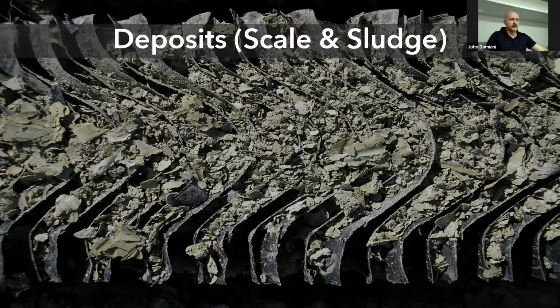Basically, a deposit is just a general term for anything that is depositing onto a surface, usually a higher skin temperature surface, so like where the heat transfer occurs, for example. So these are deposits that we don't want on the system, because a deposit is an insulating barrier to heat transfer. So if we're trying to transfer heat from a cooling system, we're trying to reject heat into the atmosphere inside the fill, or reject heat to the other side in terms of an evaporator or chiller condenser. We don't want deposits on these surfaces.